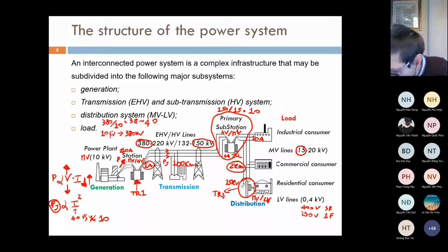So basically here, from 15,000 volts divided by 400 volts, you increase the current by almost 40 times. So instead of having 10 ampere, you will have 400 ampere. Just take this number as an example, of course, but basically instead of having 10, I will have 400 ampere.